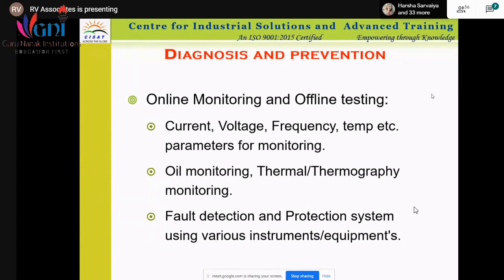Then continuous oil monitoring is possible. A thermal monitoring system is available. A thermography system is available, which will give you the temperature rise of the oil. Similarly, there is the WTI, winding temperature indicator, which will give the temperature rise in the winding. But note that there is a difference between winding temperature and oil temperature. Normally we say it's around 5 degrees centigrade. Winding temperature is always more than the oil.